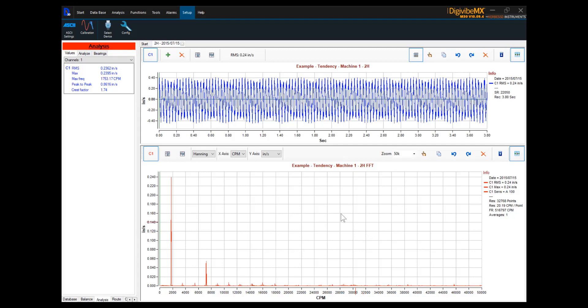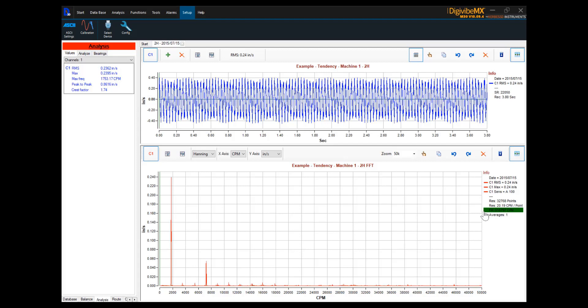As we can see in this example FFT, we have two predominant peaks, one here and one here. This FFT spectrum covers a frequency range of 516,797 CPM. It contains a possible 32,768 points of resolution, meaning that each individual peak, as we see here, covers a range of 20.19 cycles per minute.